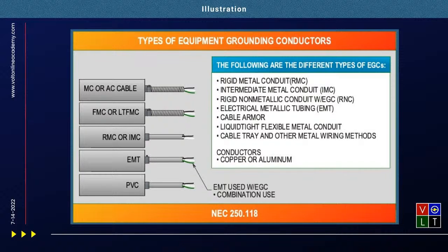To be honest, EMT that doesn't even have a set screw tight in the fitting is probably going to be just as good of a ground as an equipment grounding conductor in there. But without that screw being tight, it's not assured - it's not an assured grounding path.